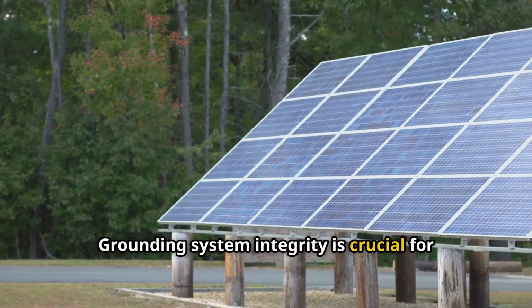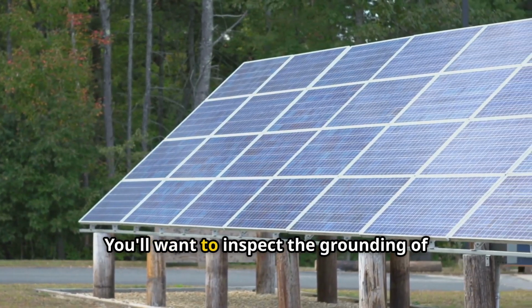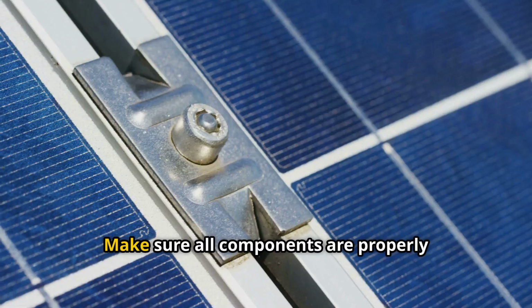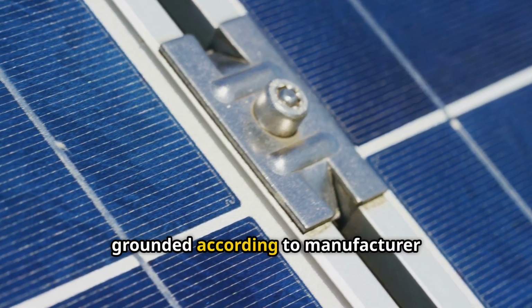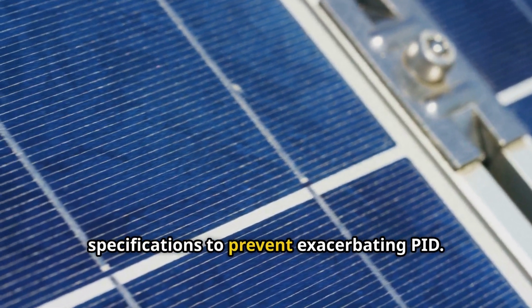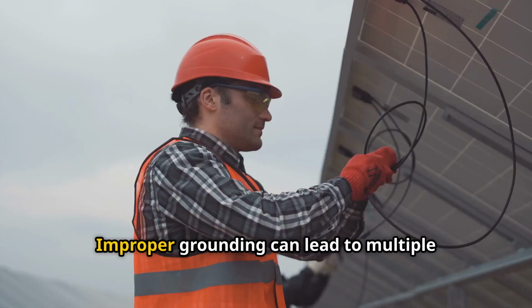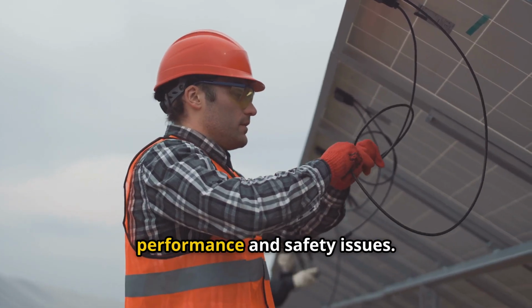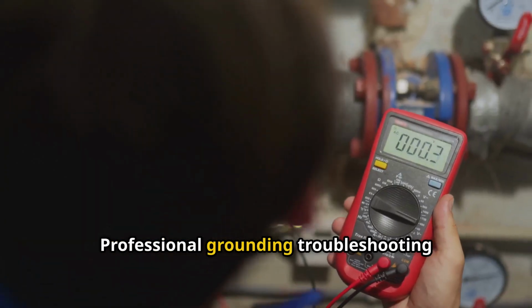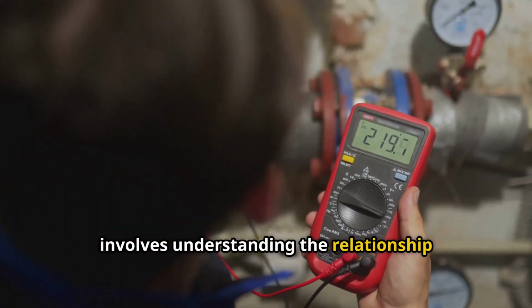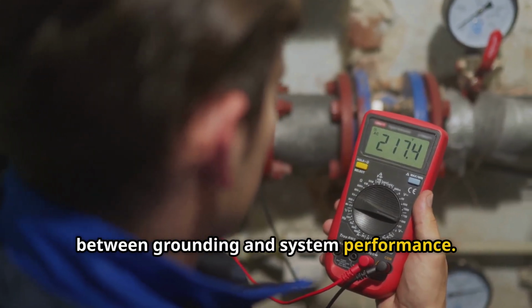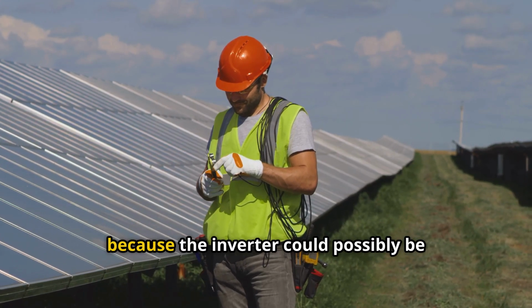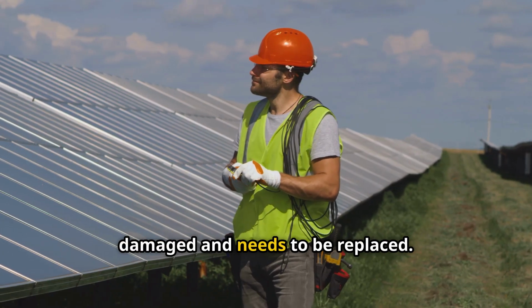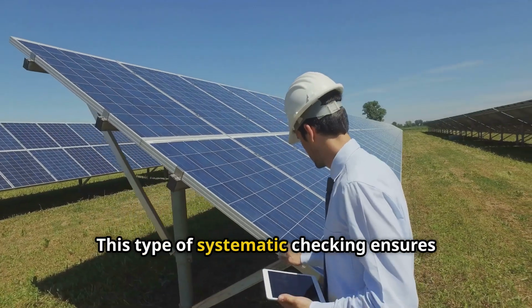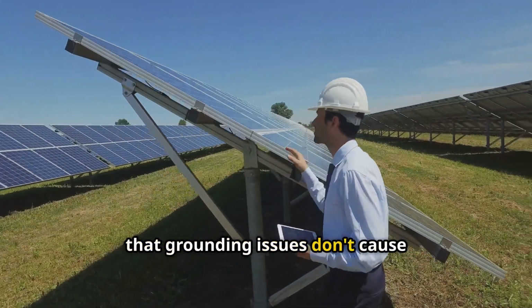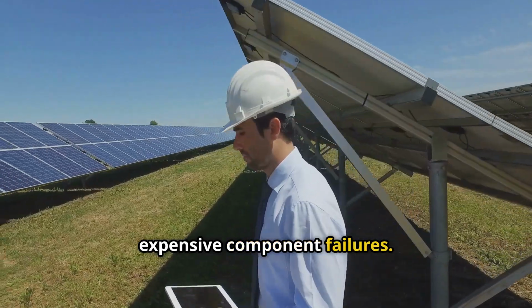Grounding system integrity is crucial for both performance and safety. You'll want to inspect the grounding of your solar system. Make sure all components are properly grounded according to manufacturer specifications to prevent exacerbating PID. Improper grounding can lead to multiple performance and safety issues. Professional grounding troubleshooting involves understanding the relationship between grounding and system performance. The battery connection should be checked because the inverter could possibly be damaged and needs to be replaced. This type of systematic checking ensures that grounding issues don't cause expensive component failures.